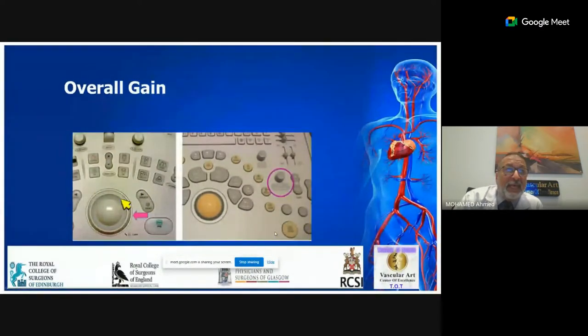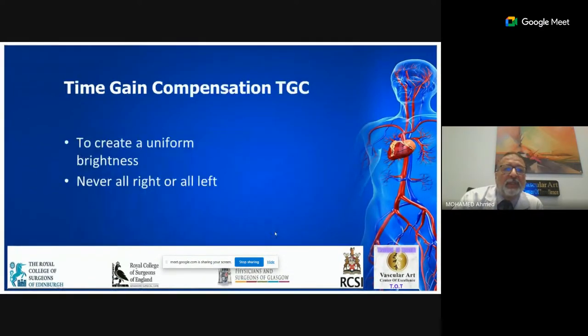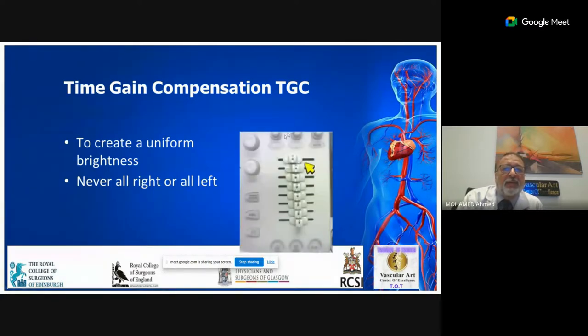And this is the gain. If you want to improve the picture, you increase the gain, and I will show you the button to increase the gain. There is the time gain compensation button, which in the new machine is not found anymore, but in the old machine, they look like this. When you use these TGC buttons, you get more gray B-mode, to be more elaborate, more clear.